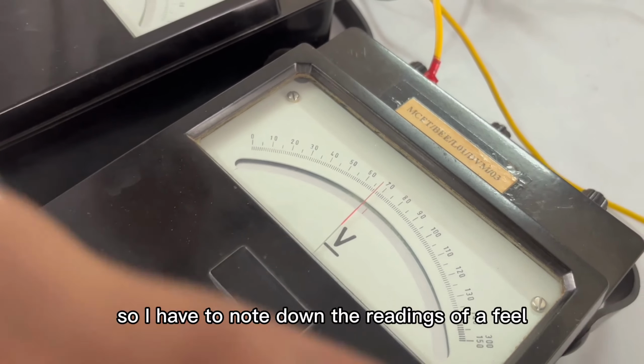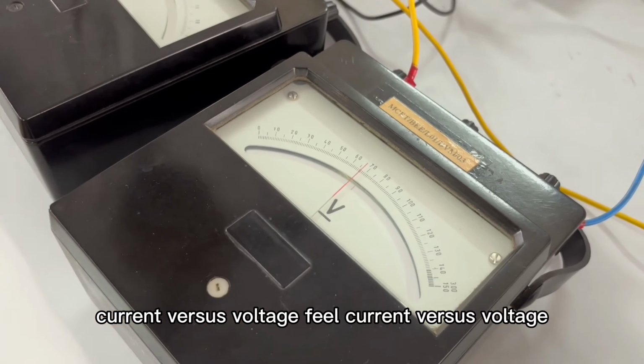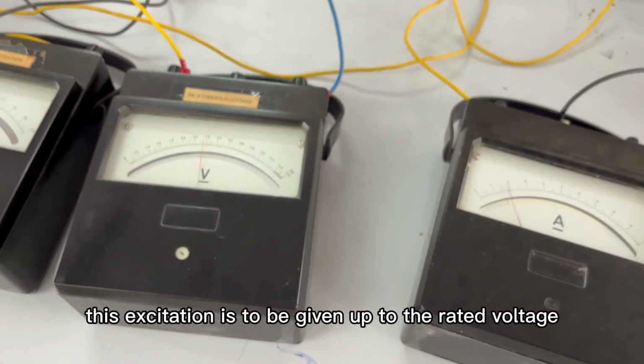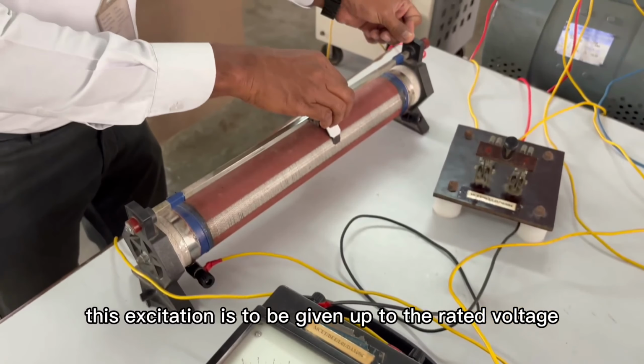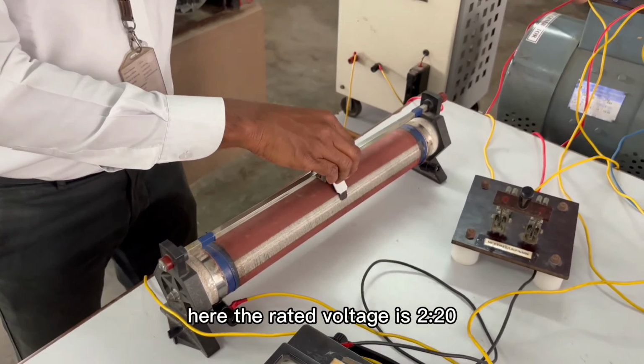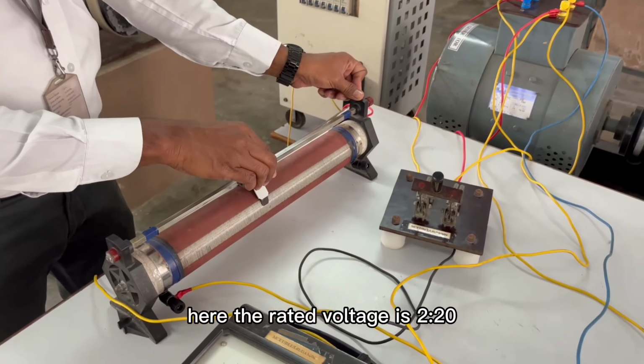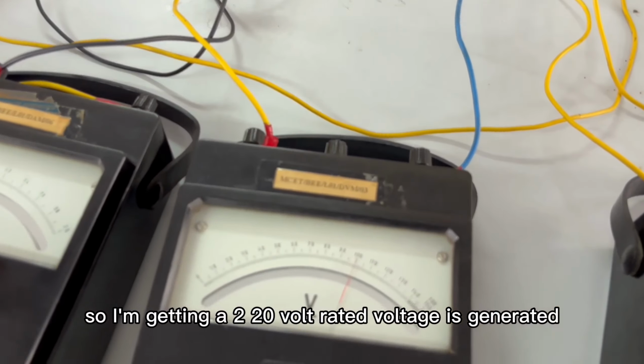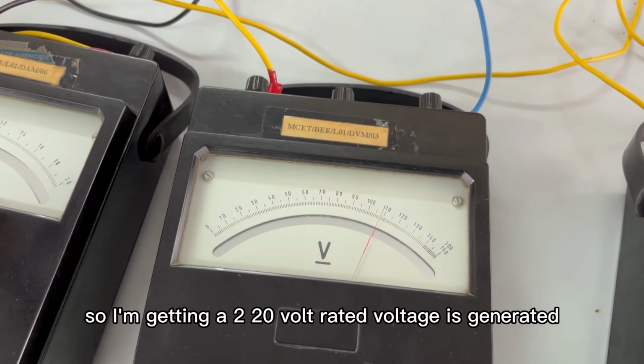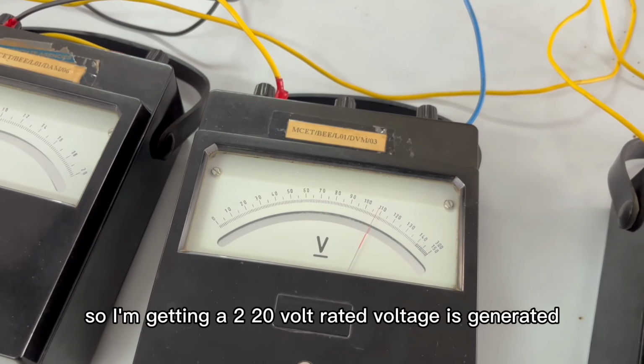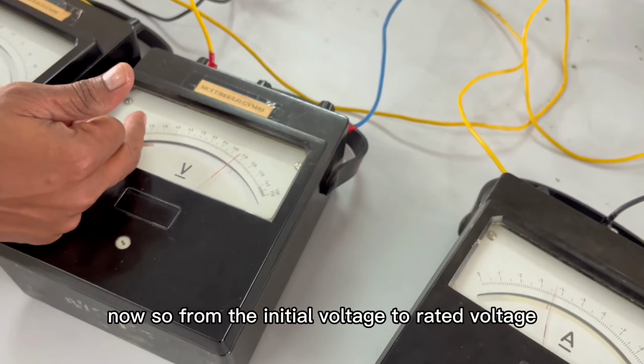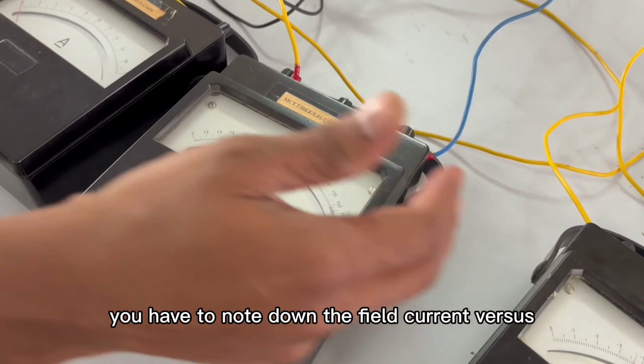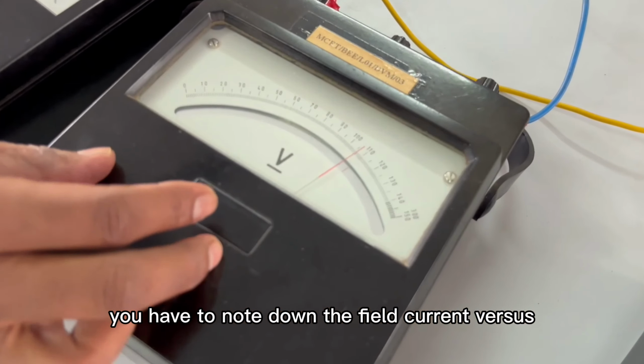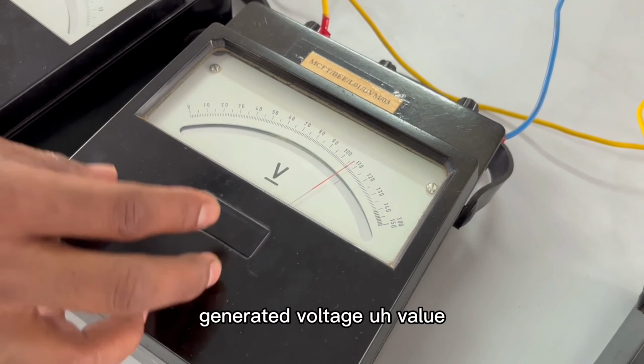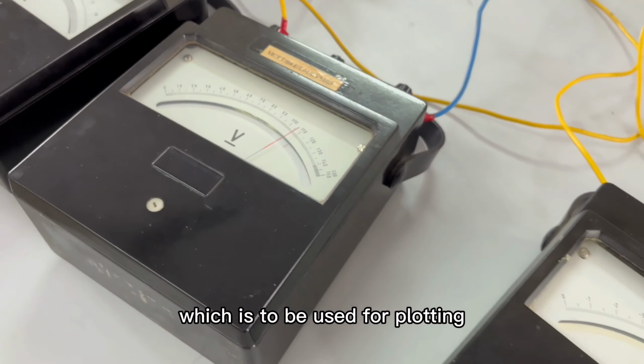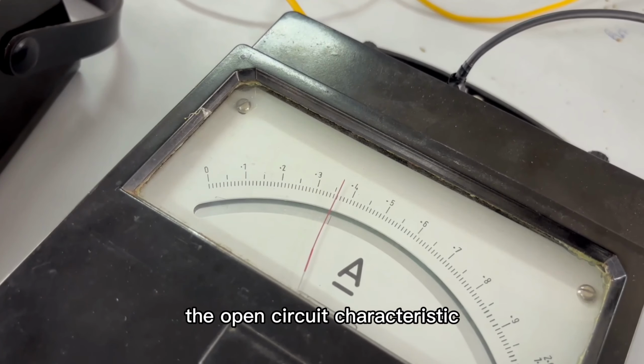So I have to note down the readings of field current versus voltage. This excitation is to be given up to the rated voltage. Here the rated voltage is 220, so I am getting the rated voltage of 220 volt generated now. So from the initial voltage to the rated voltage, you have to note down the field current versus generated voltage values, which are to be used for plotting the open circuit characteristic.